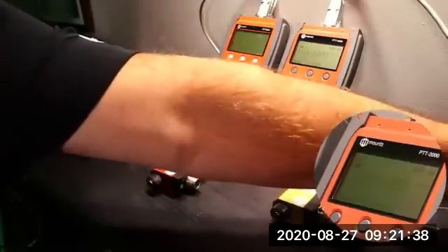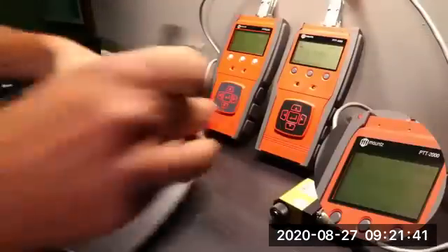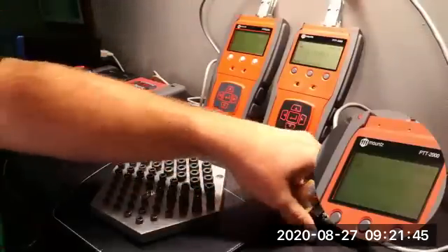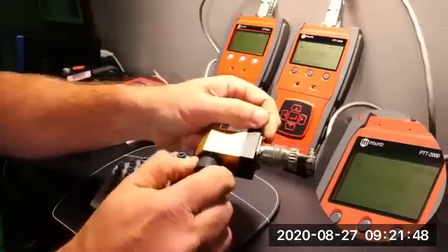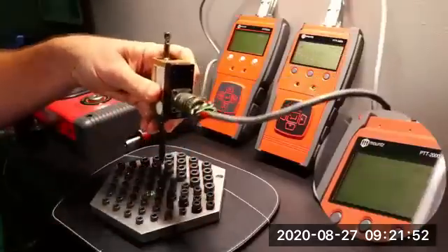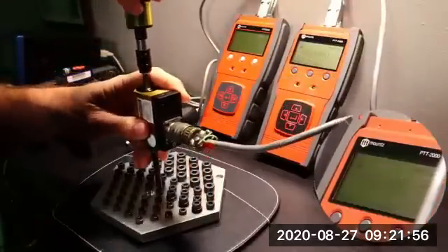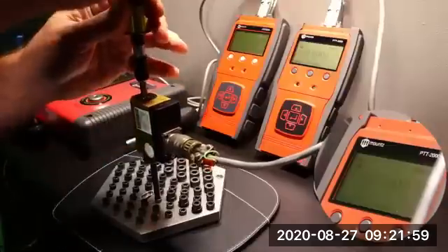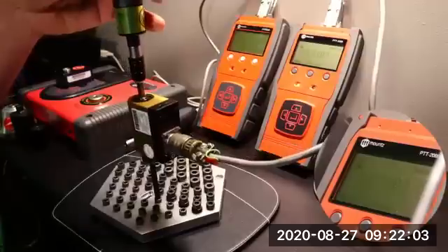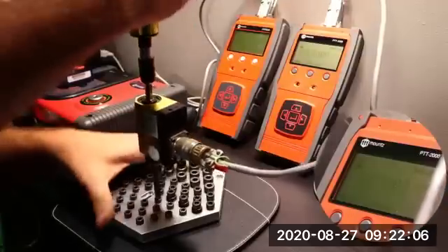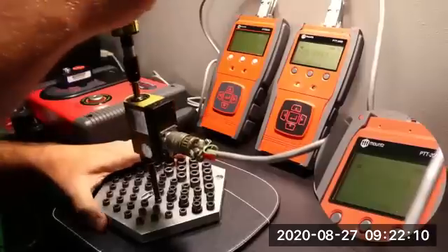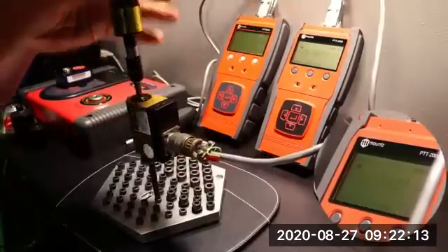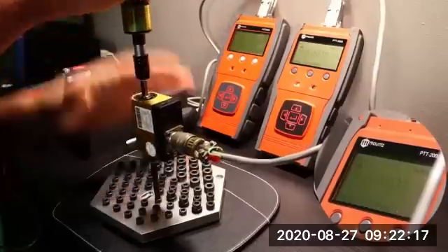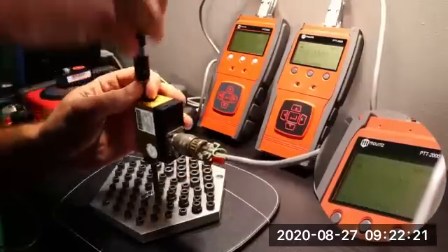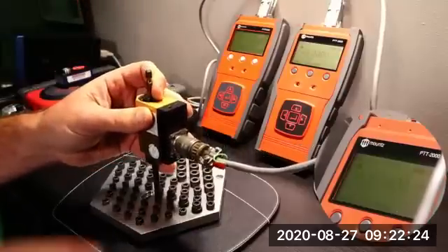So the rotary style transducer, we do have the ability to test with it. Again, this can be used with a power tool, a hand tool, and also a static tool. If we want to see what value we are getting, we can get our values from our screwdriver, and it's going to be a little different than what we may see on our analyzer because of the different joint characteristics. If we wanted to use our power tool for this, we could certainly do that as well.